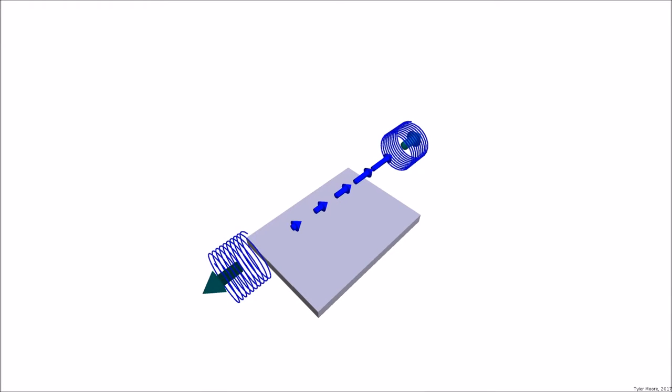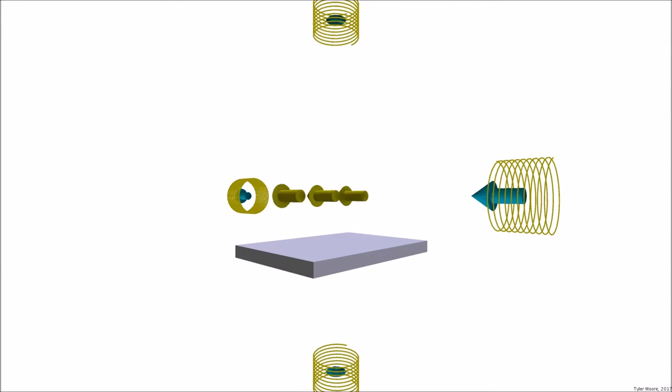and the blue coils along the z-axis. Next are the transmit coils. These are oriented to impose a magnetic field perpendicular to the z-axis. They are run out of phase so that the magnetic field they generate rotates within the xy plane.